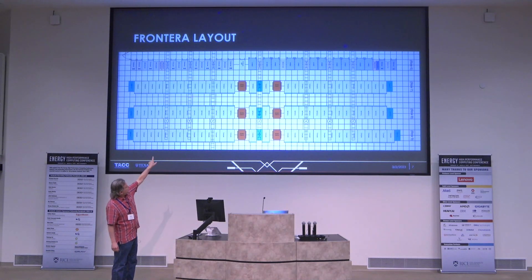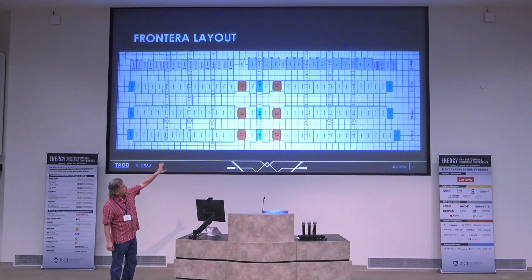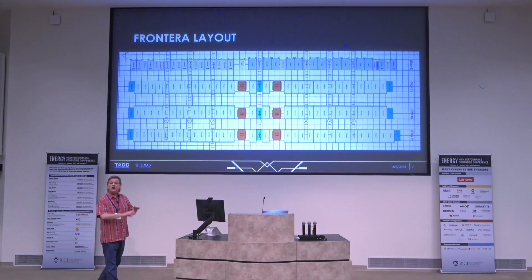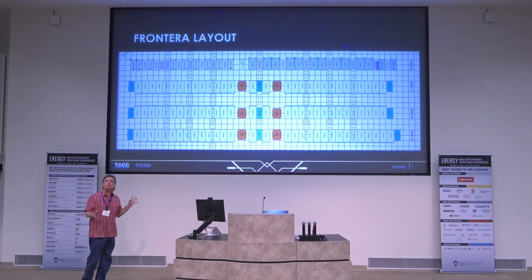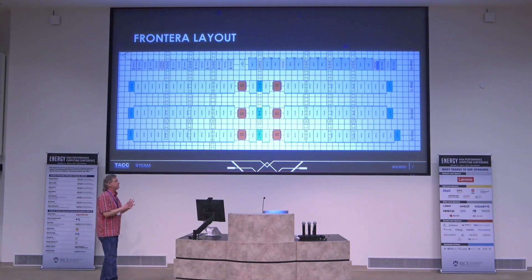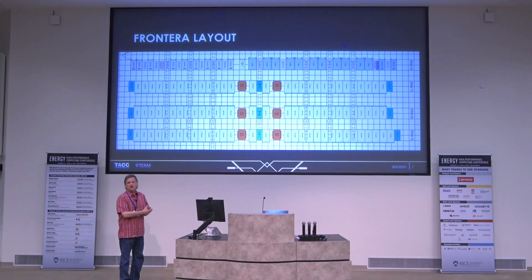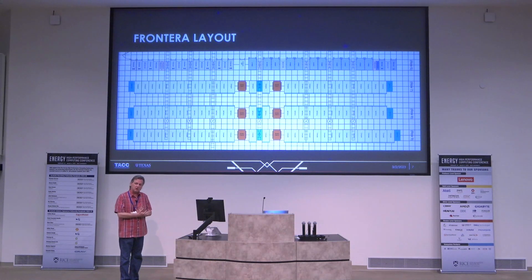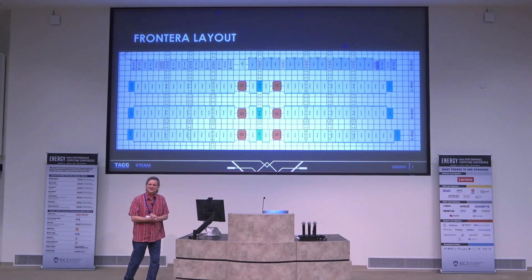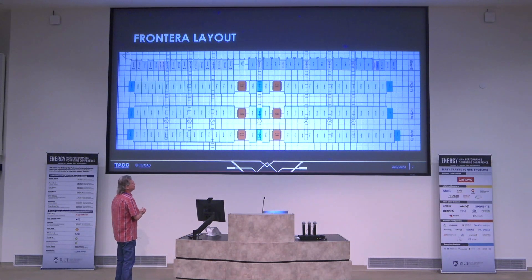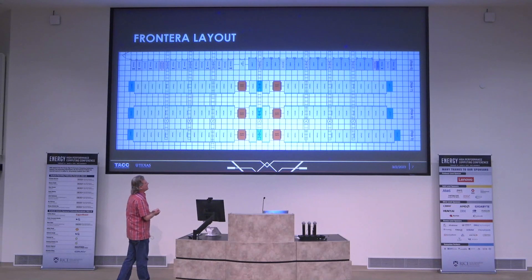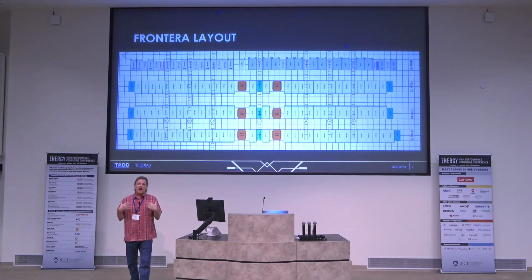The storage is located at the top row and we have UPS in the data center that feeds just the storage and switches — we do not keep the compute hardware on UPS, as that's way too much power. Frontera at full bore during LINPACK runs about five and a half megawatts of total power. Interestingly, the core director-class switches are also liquid-cooled, so liquid cooling is coming for networking hardware as well.